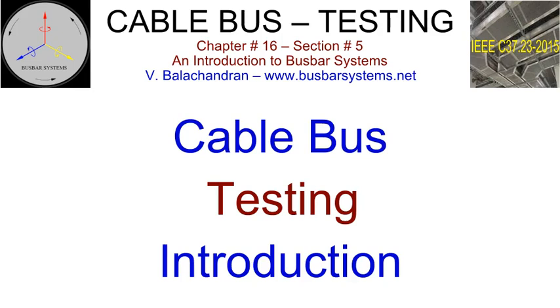Cable bus. Testing. Introduction. In the absence of a dedicated recommendation from the International Electrotechnical Commission, the cable bus is tested using IEEE C37.23 year 2015 standards as a guiding document. Cables are tested and certified as per relevant ANSI/IEEE standards or International Electrotechnical Commission recommendations by the cable manufacturer. Since the cables used in cable bus for medium voltage are shielded, impulse voltage withstand test on the cable bus assembly is redundant and need not be performed. Its performance will not be affected by the presence of other earthed conductors.